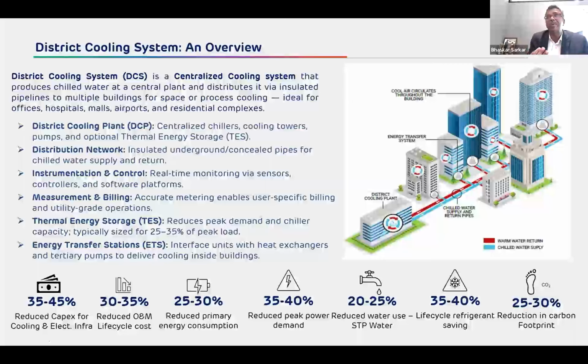One is less quantity, two is zero leakage, and three is the refrigerant type used, which is low on GWP. So the refrigerant has a triple positive effect on the atmosphere if we use DCS. Overall, all this would lead to a 25 to 30% reduction in the carbon footprint. So these are the benefits of a DCS system.